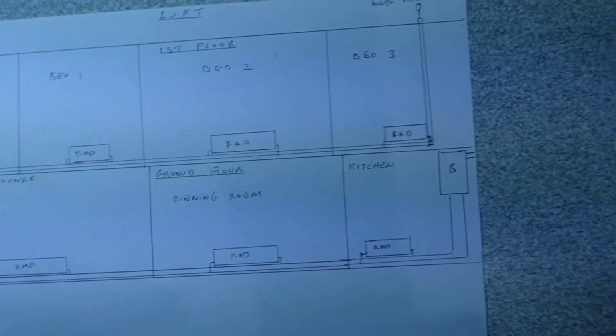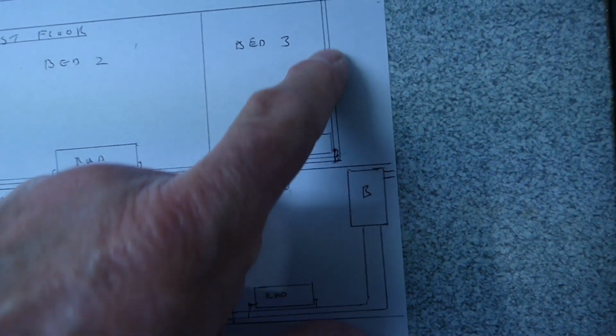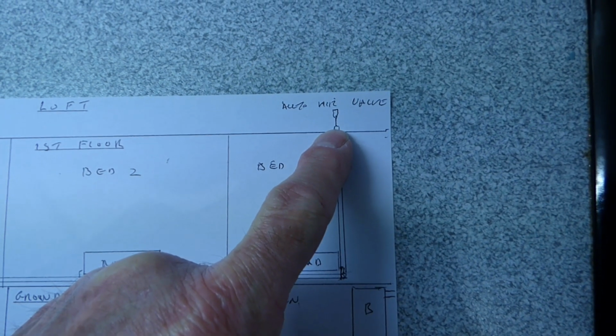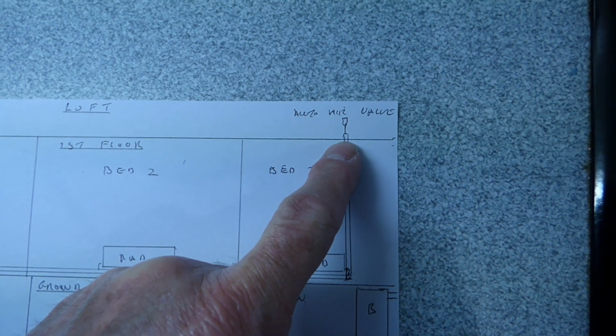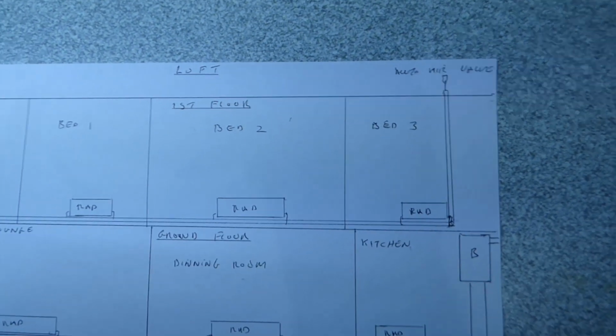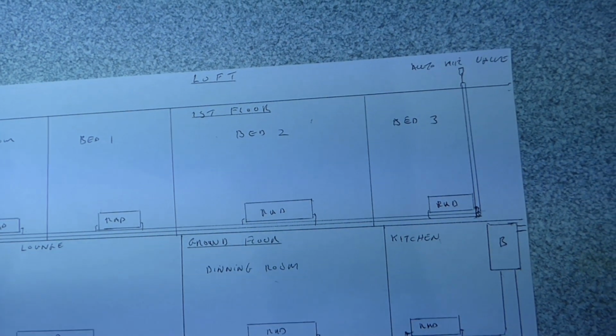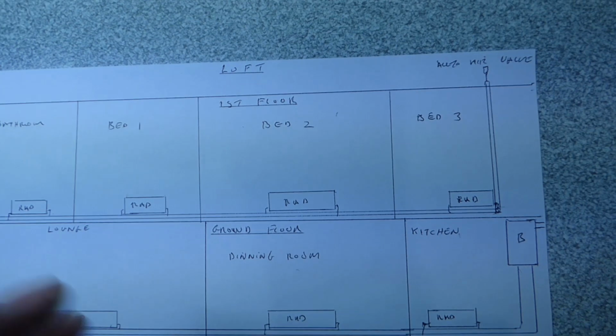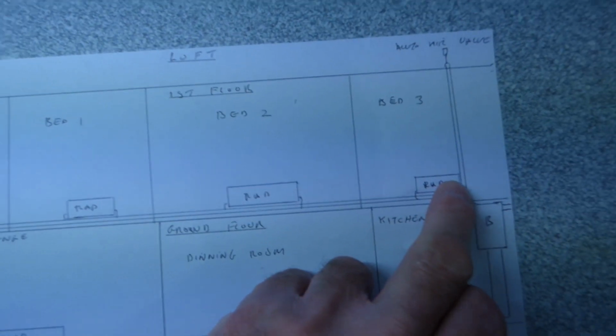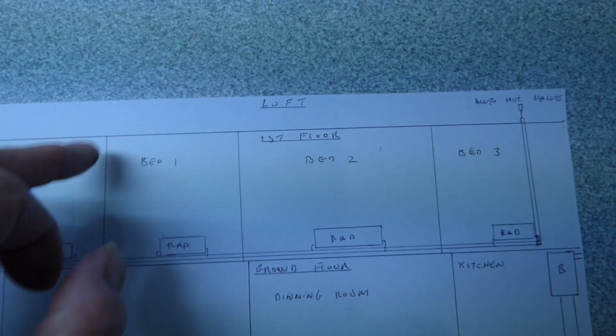Well, I had a good tip from friend John, good subscriber man. As you can see, what I've drawn in here is two pipes that come off the flow and the return coming back down, and on top of that is what's called an auto air valve that you can fit yourself in the loft. The fact it's up there in the loft means that any air produced anywhere in this system will be vented up there. Now, I know it's not ideal to have two pipes going up a bedroom wall, but if you've got a cupboard somewhere that you could hide those pipes away, then it would be a great idea. You'd forget your air problem altogether. It doesn't have to be where I've drawn, it could be here, there and there. It doesn't matter as long as it's vented up into the loft.